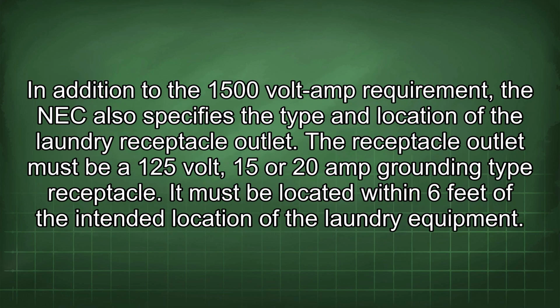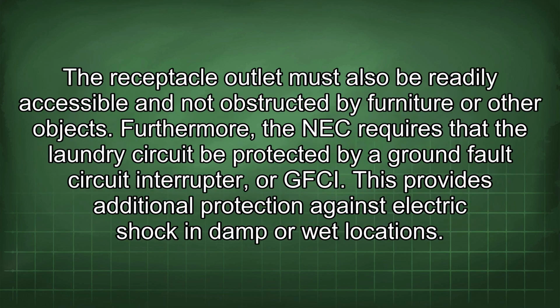In addition to the 1500 volt amp requirement, the NEC also specifies the type and location of the laundry receptacle outlet. The receptacle outlet must be a 125 volt, 15 or 20 amp grounding type receptacle. It must be located within 6 feet of the intended location of the laundry equipment. The receptacle outlet must also be readily accessible and not obstructed by furniture or other objects.